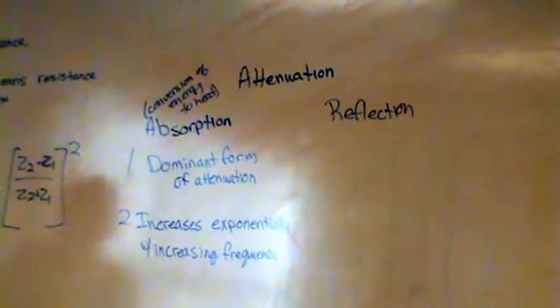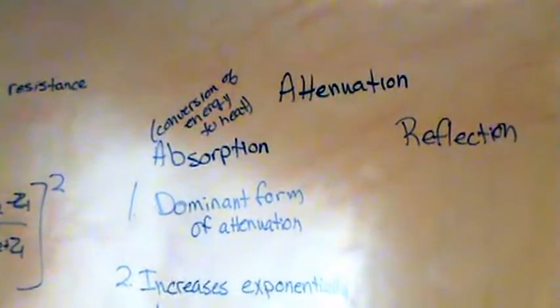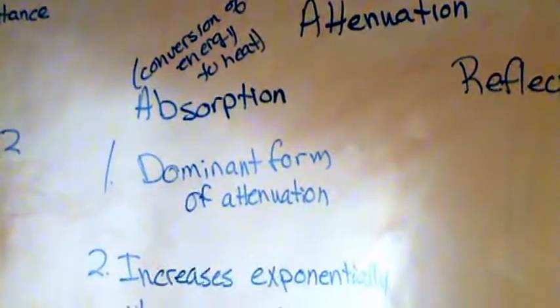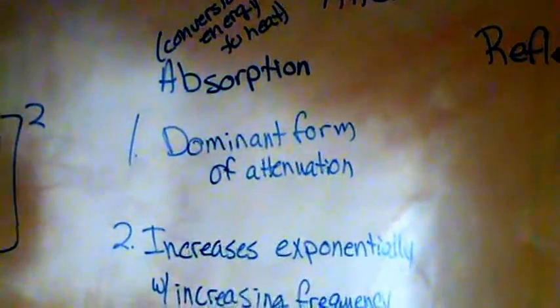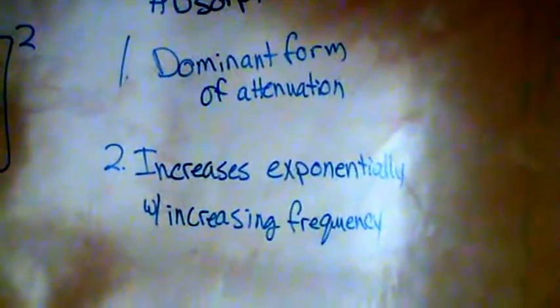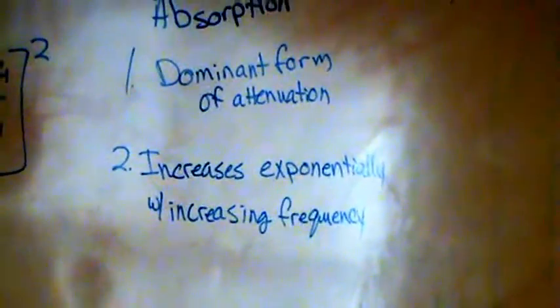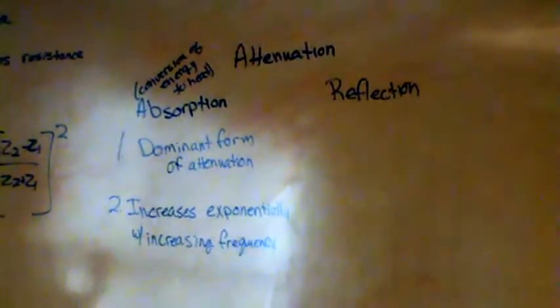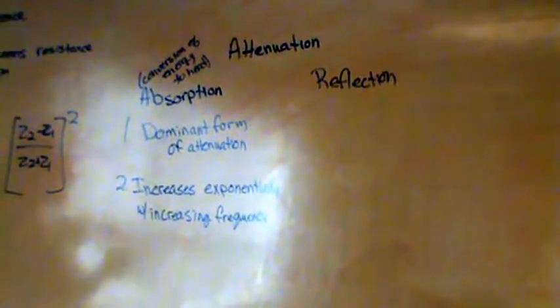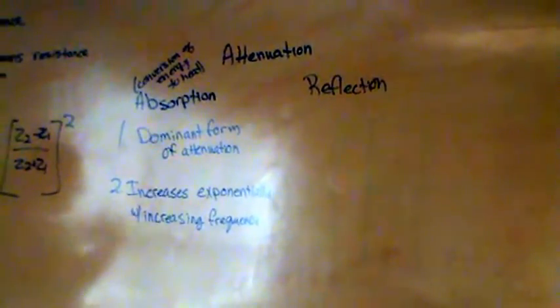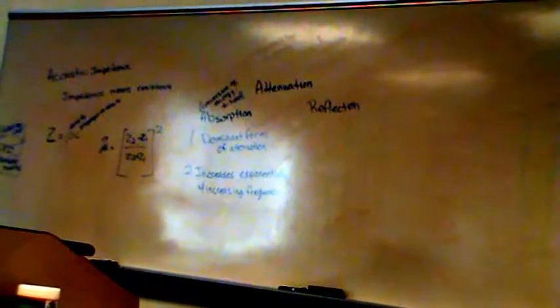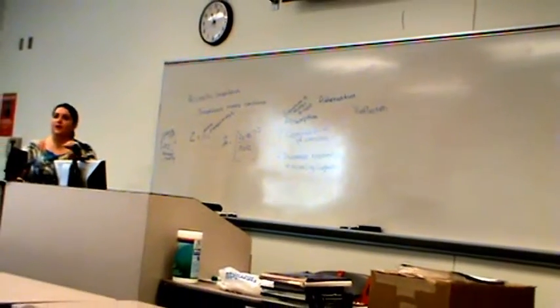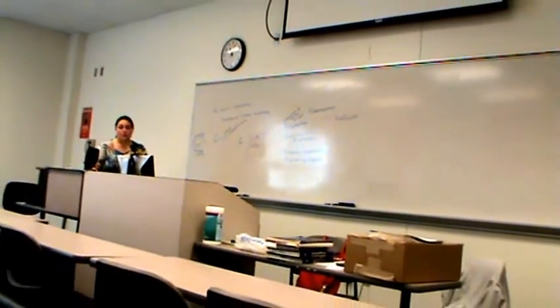Okay, so that's all you really need to know about absorption. It's that conversion of energy into heat. It's the dominant form of attenuation. That means that as the wave is interacting with the medium, most of our ultrasound energy that's lost is converted to heat. So we have very little that's reflected back to the transducer because a lot of it is lost to absorption. And then we have that refraction thing. Refraction bends the beam off in different directions, so it doesn't even come back to the transducer a lot of the time. But the main thing that weakens or decreases the amount of power that comes back to the transducer out of the body is absorption. So a lot of the ultrasound energy is converted into heat.